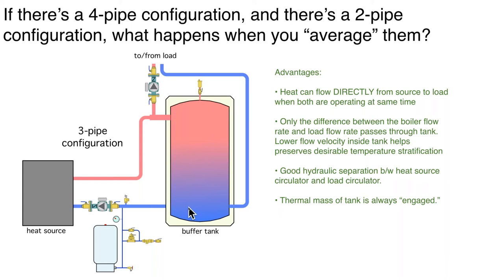I really like this buffer configuration for a heat pump. If you're doing a geothermal heat pump — water to water — or you're doing an air-to-water heat pump, this is a really good configuration for the tank. Because what this does is it ensures that you're always engaging the thermal mass. Anytime that load is on or the heat source is on, there's going to be flow going through that tank.